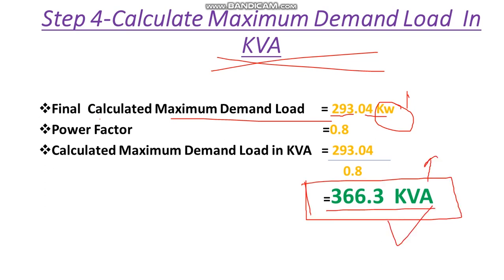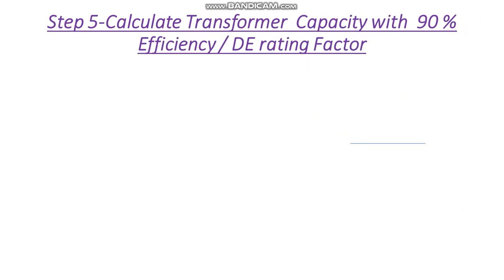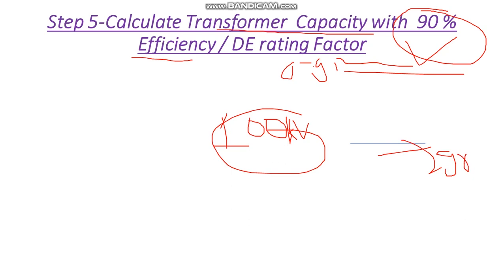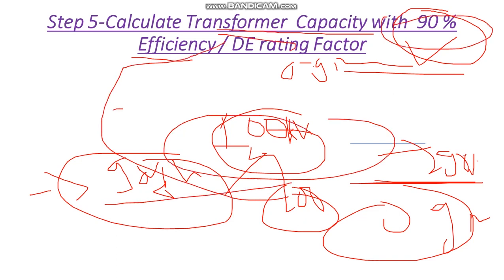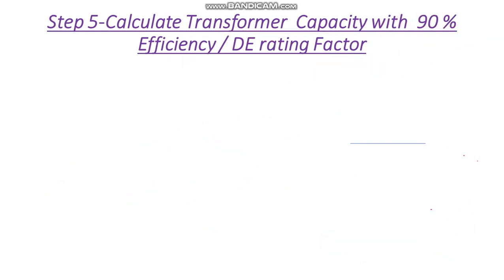In Step 5 we calculate the transformer capacity with 90% efficiency, or a derating factor of 0.9. This means that for a 100 kVA transformer with 90% efficiency, we should only connect up to 90 kVA of load. If we connect more than 90 kVA — say 95 kVA — the transformer would be overloaded and would not operate at its efficiency level. That's why we must select the transformer size considering this 90% efficiency.